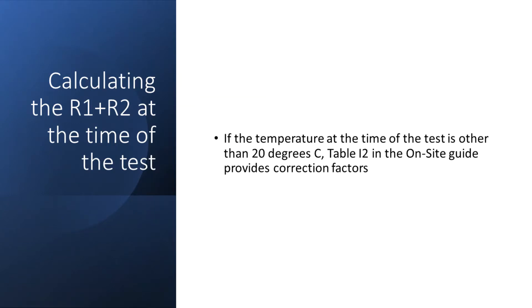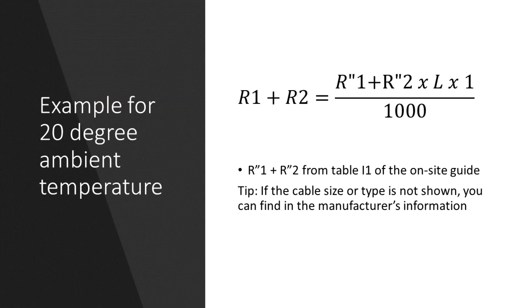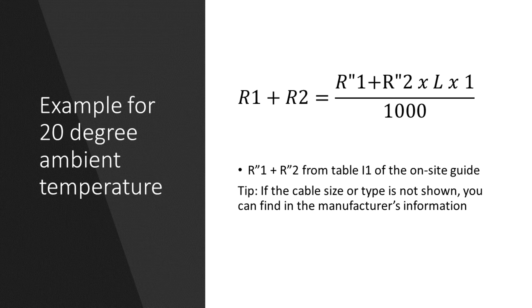So to calculate what the R1 plus R2 will be at the time of the test, we can use the correction factors on the next page in the on-site guide on table I2 which gives correction factors for various ambient temperatures. However, if the ambient temperature is 20 degrees C then the factor is 1, because the values for milli-ohms per meter are based on 20 degrees C.